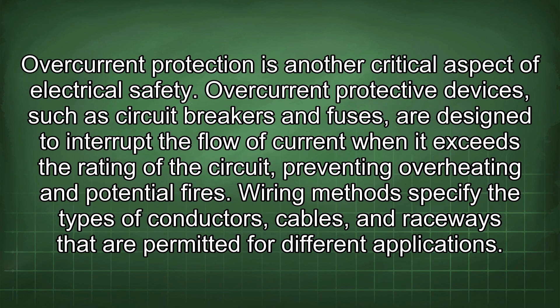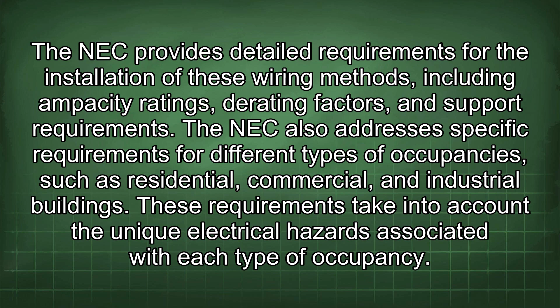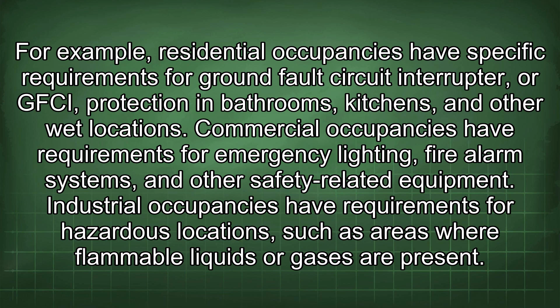The NEC also addresses specific requirements for different types of occupancies, such as residential, commercial, and industrial buildings. These requirements take into account the unique electrical hazards associated with each type of occupancy. For example, residential occupancies have specific requirements for ground fault circuit interrupter, or GFCI, protection in bathrooms, kitchens, and other wet locations. Commercial occupancies have requirements for emergency lighting, fire alarm systems, and other safety-related equipment. Industrial occupancies have requirements for hazardous locations, such as areas where flammable liquids or gases are present.